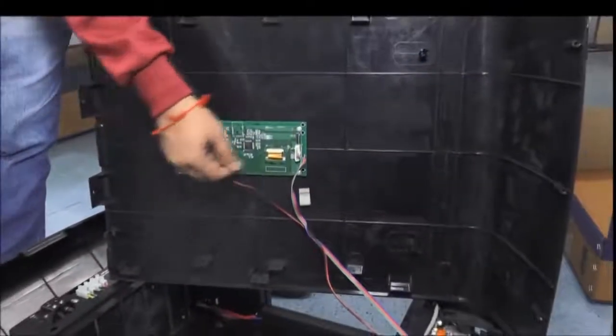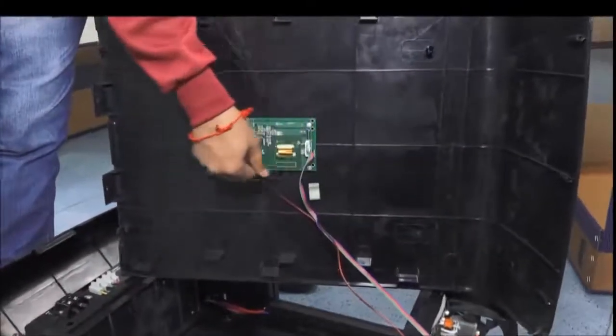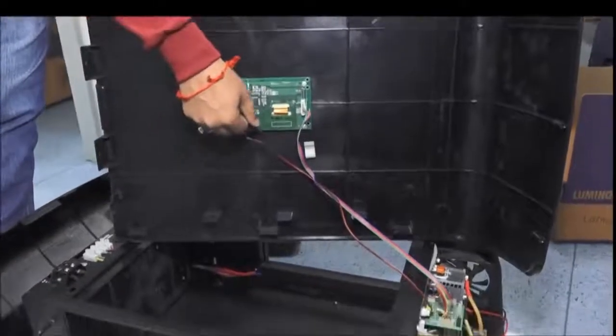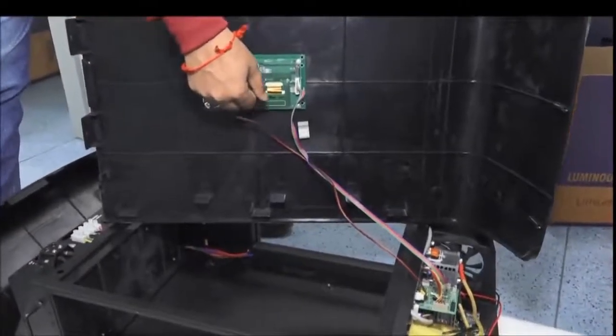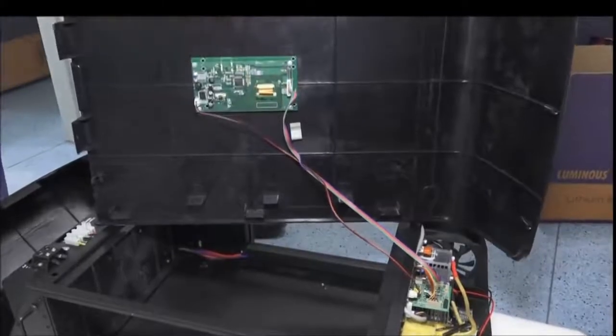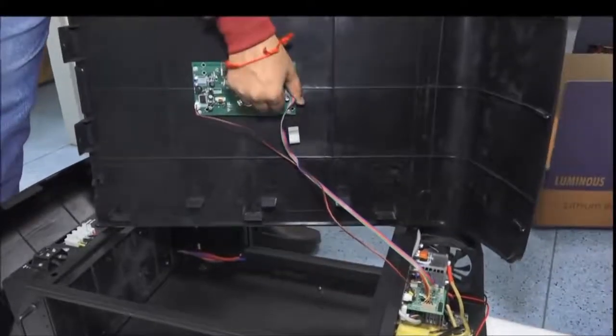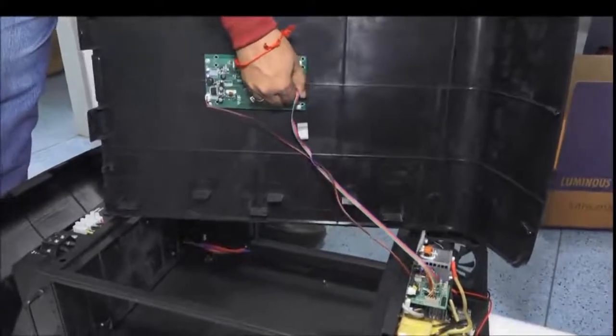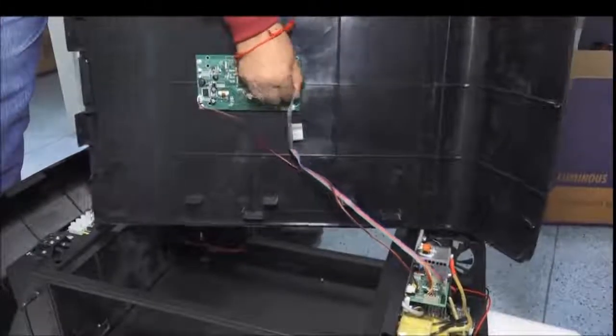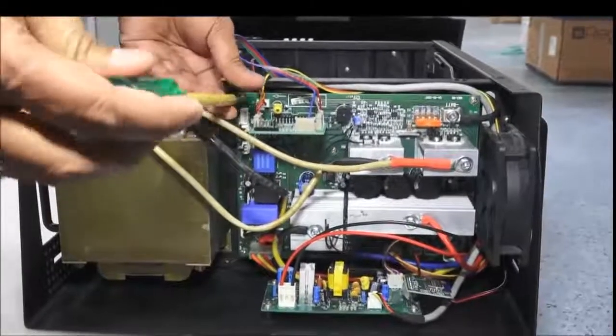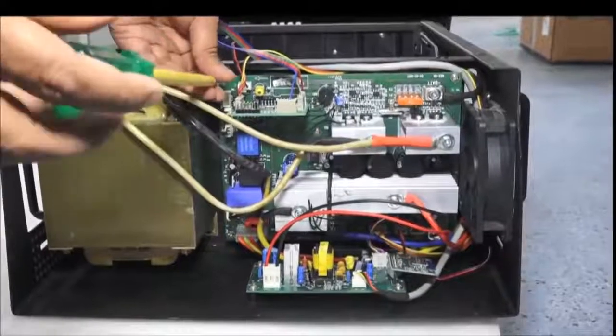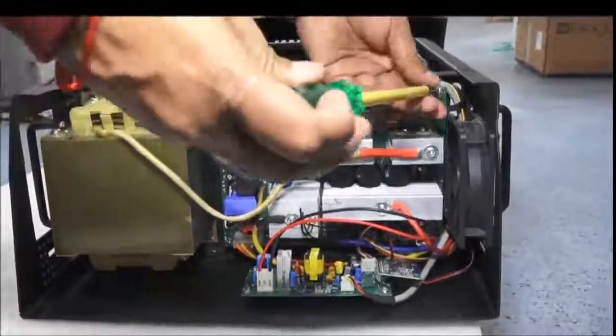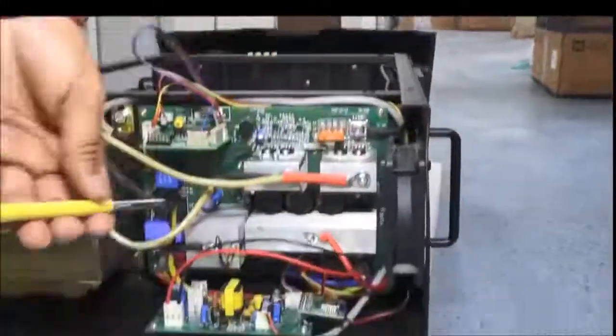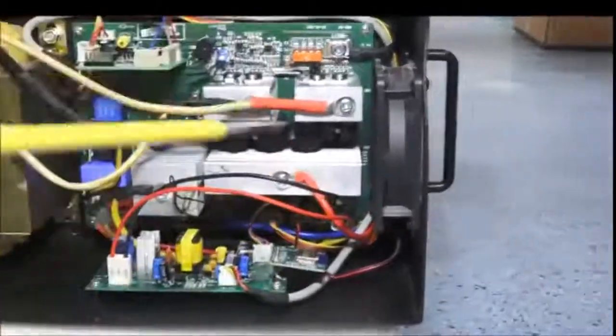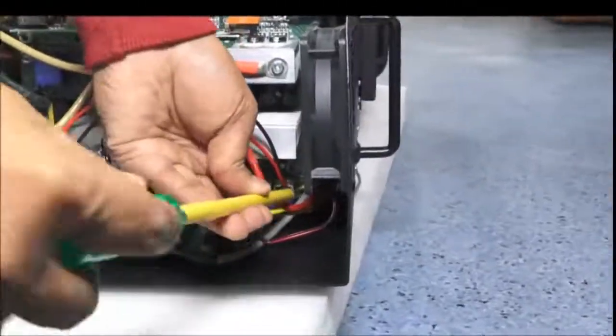Now, if you want to remove the touchscreen, you can do it by opening the four screws and two connectors as shown before. To connect the new touchscreen, first connect the two connectors and then screw it in. You can now access the power PCB board as well. To remove the power PCB, open the screws as shown and remove the connectors. These are the screws that need to be opened.